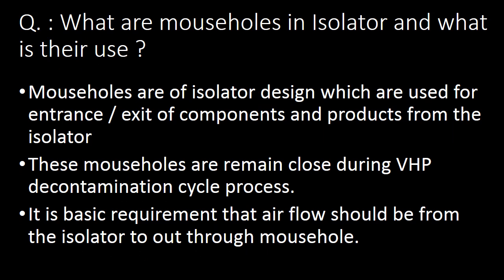Next question: what are mouse holes in an isolator and what is their use? Mouse holes are an isolator design feature used for the entrance and exit of components and products from the isolator. These mouse holes remain closed during the entire VHP decontamination process. A basic requirement is that airflow should be from inside the isolator to outside through the mouse hole.